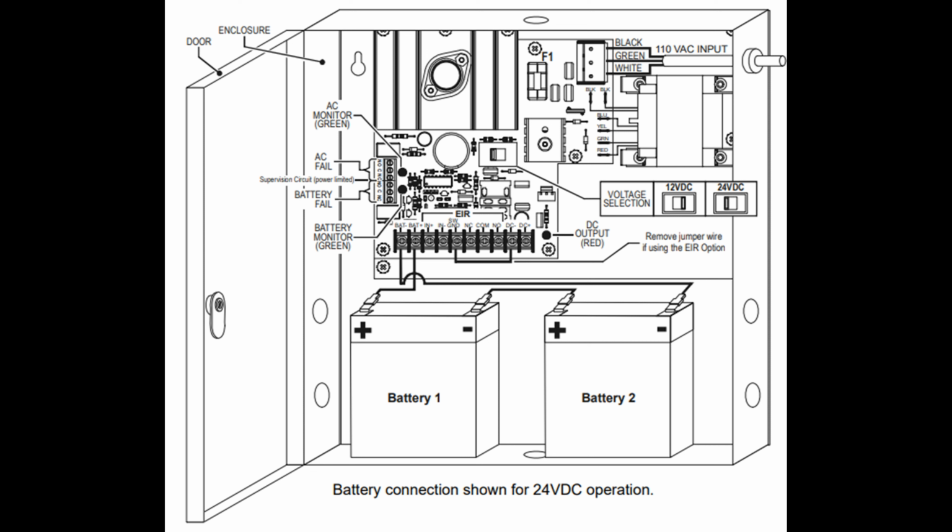He wasn't really sure, when I spoke to the client, whether he was doing fail-safe or fail-secure. If it's fail-secure, he's only going to power that circuit when he wants to unlock the strike. In that event, you wouldn't need battery backup, in my opinion. But if he wants fail-safe, so he's continuously powering the strike, then he needs battery backup in the event that power goes out.